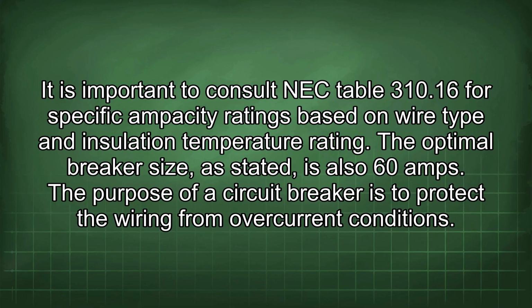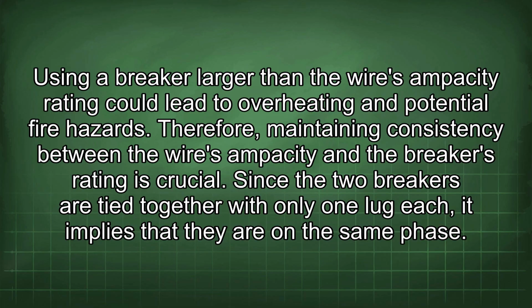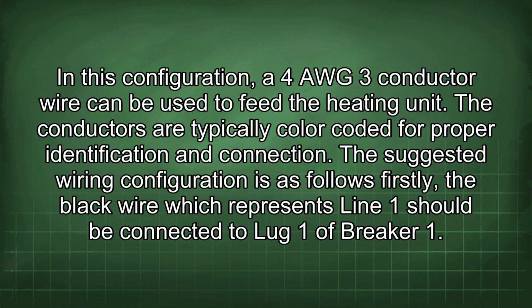The purpose of a circuit breaker is to protect the wiring from overcurrent conditions. Using a breaker larger than the wire's ampacity rating could lead to overheating and potential fire hazards. Therefore, maintaining consistency between the wire's ampacity and the breaker's rating is crucial. Since the two breakers are tied together with only one lug each, it implies that they are on the same phase. In this configuration, a 4 AWG 3-conductor wire can be used to feed the heating unit.